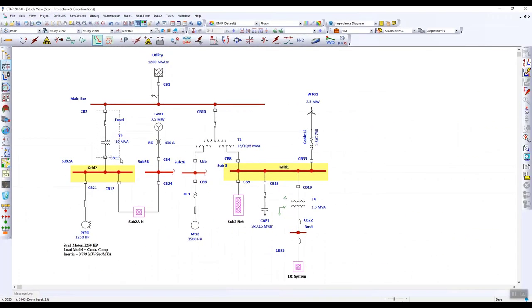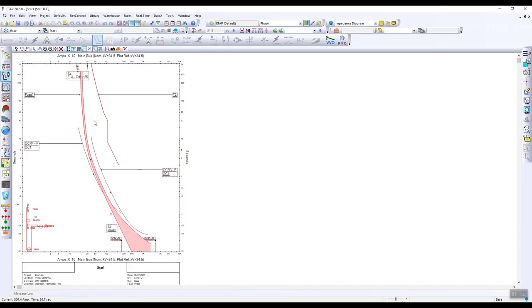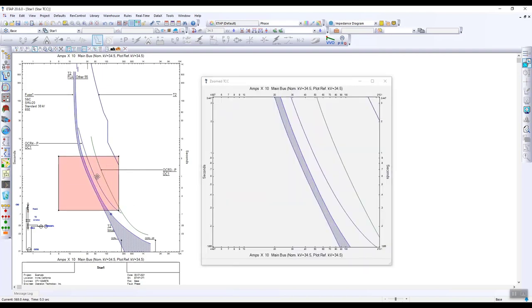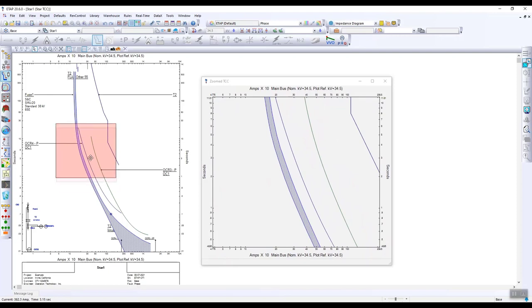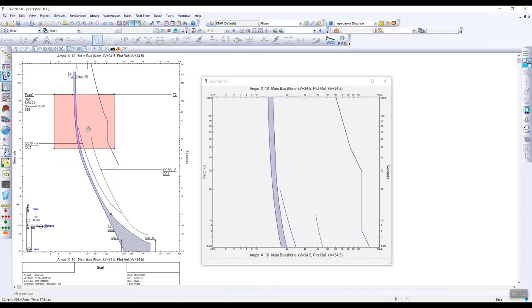We can create time current curves by selecting the network we would like to evaluate. Here on the bottom left, we have the network shown. I'm going to add a label to this fuse so that we can see the settings. If I move the fuse curve to the left or right, we can see all the available sizes. I'm going to use the zoom tool so I can take a closer look at the TCC curve. If I move the zoom box up and down, you'll see that it updates on the right dynamically.